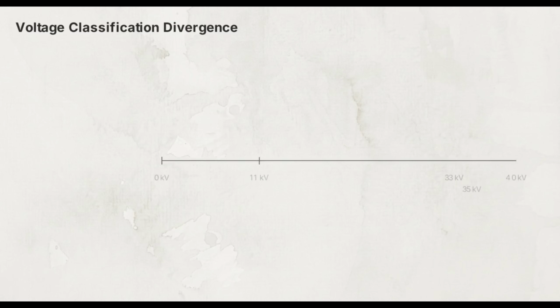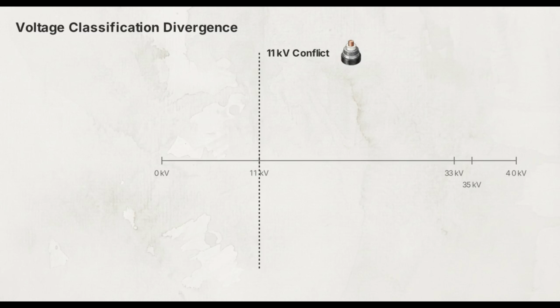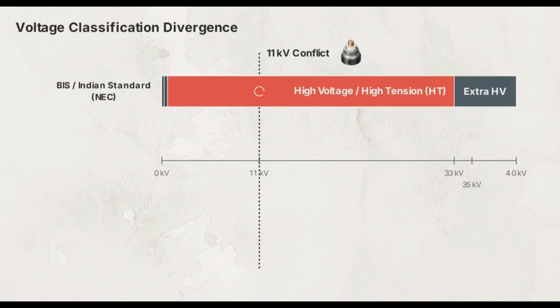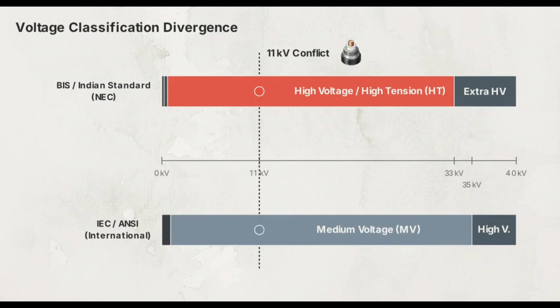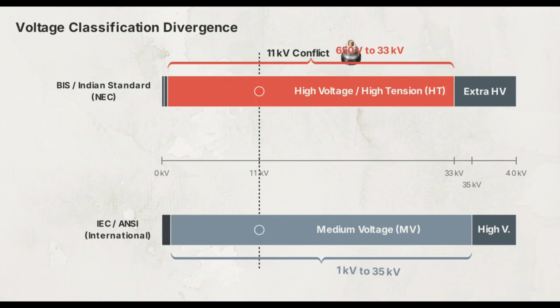At the 11 kilovolt threshold, Indian standards classify the asset as high voltage, while IEC and ANSI label it medium voltage. Legacy Indian rules force loads between 650 volts and 33 kilovolts into high tension. Conversely, international standards treat this exact load as standard medium voltage. This forces manufacturers into a dual-layered engineering strategy, meeting global physical performance benchmarks while adhering to contradictory domestic labeling and certification laws.